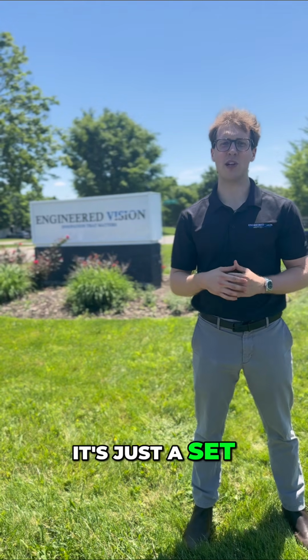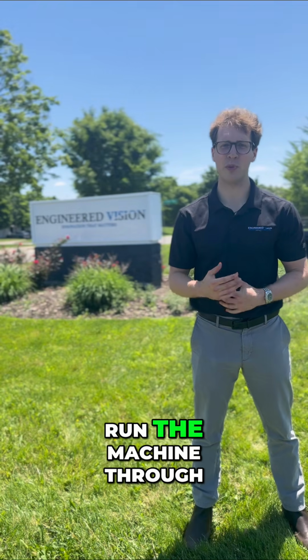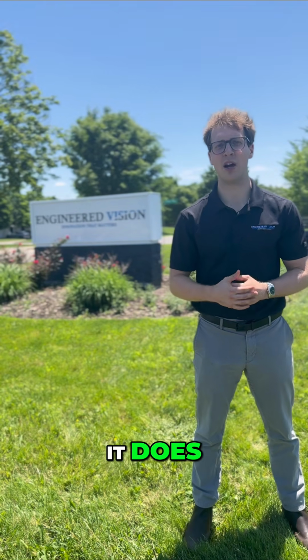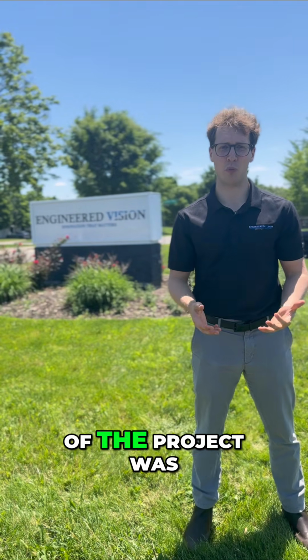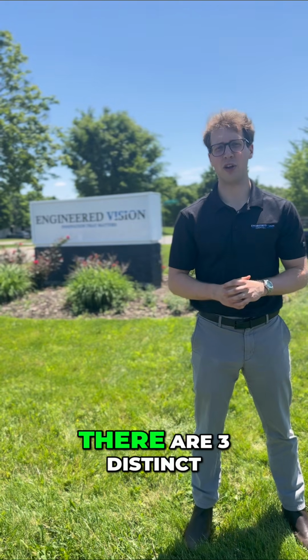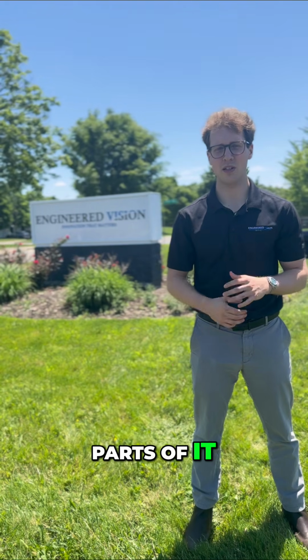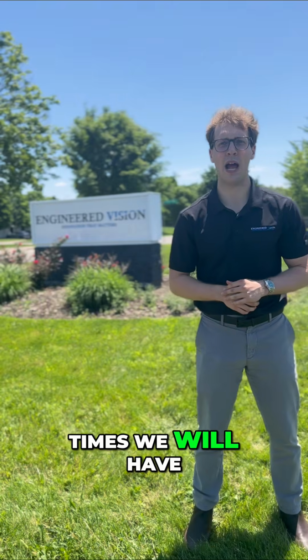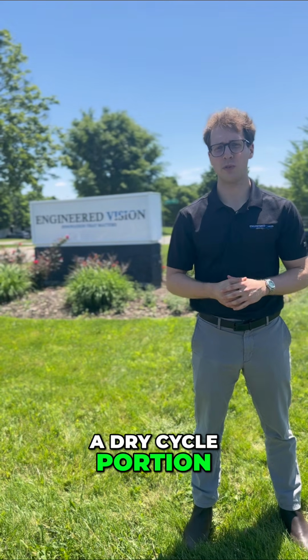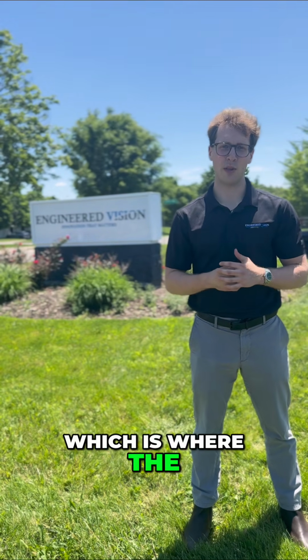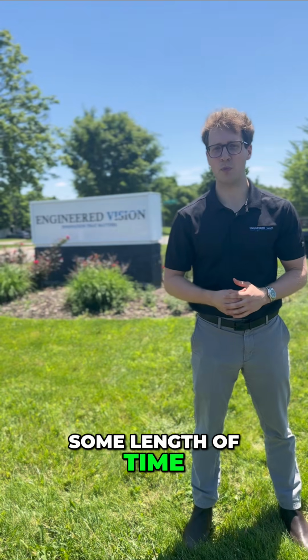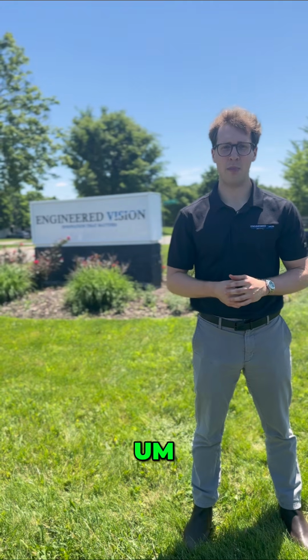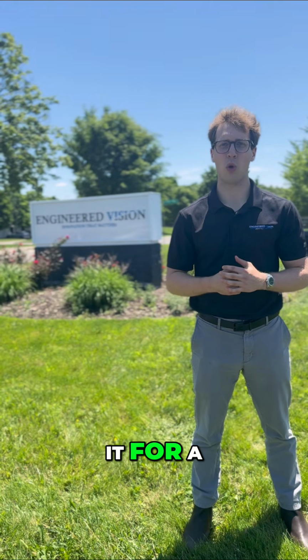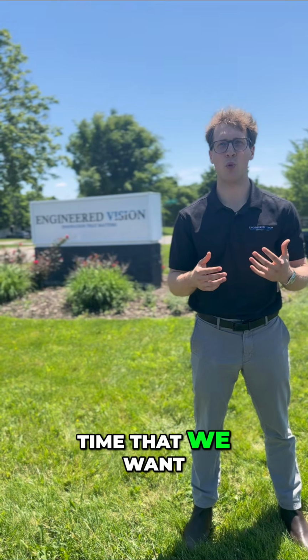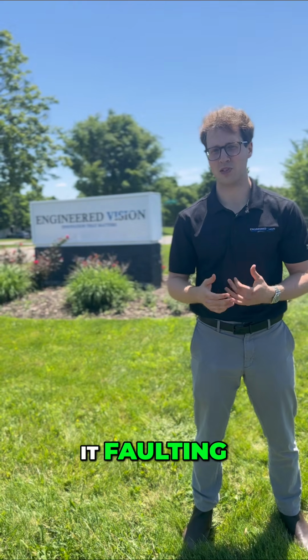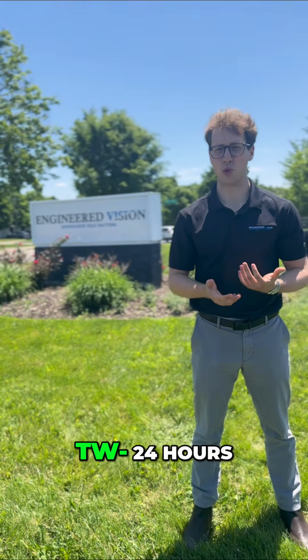And it's just a set of requirements that we run the machine through to make sure that it does what the original scope of the project was. Typically there are three distinct parts of it. A lot of the times we will have a dry cycle portion for FAT, which is where the machine will run for some length of time without any parts in it. And we will run it for a set amount of time that we want to get through without it faulting. So we'll typically look for 24 hours.